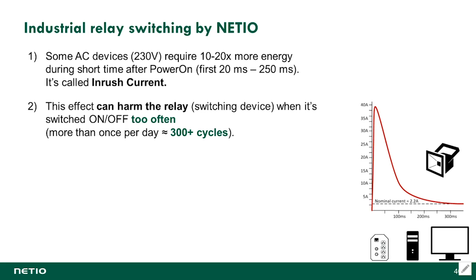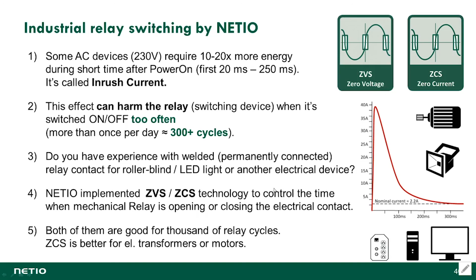And if you are switching this device 5 or 10 times per day, it really becomes the lifetime limiter. So what NETIO does is implement a special technology for timing the switching of the relay, which we call zero voltage switching or zero current switching. In the end, our relays survive much longer.